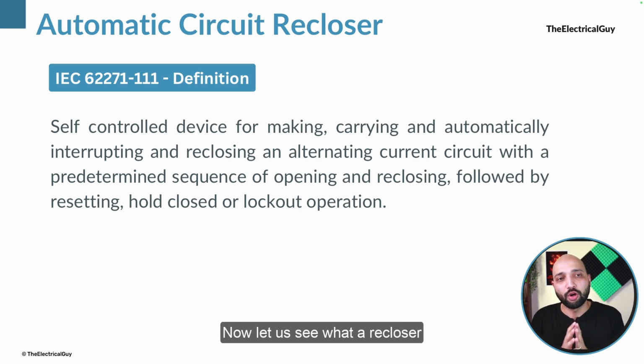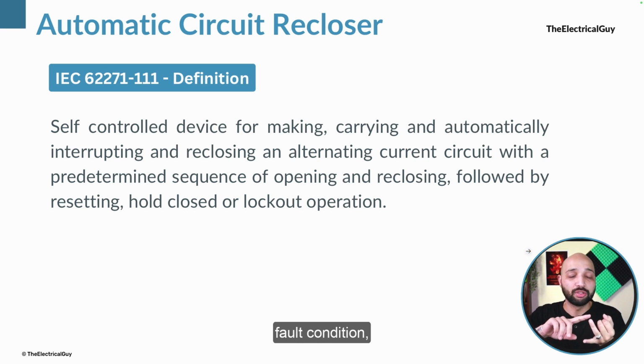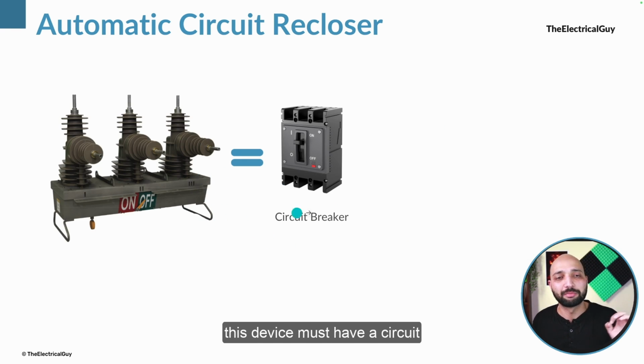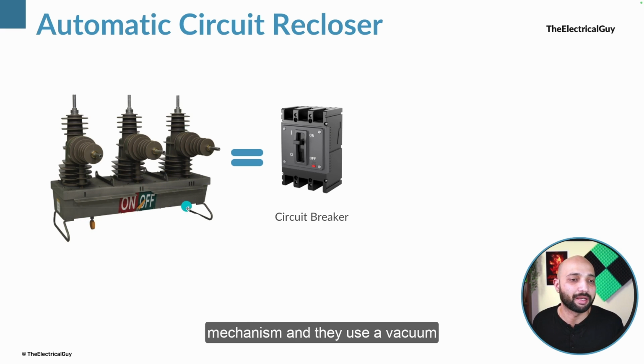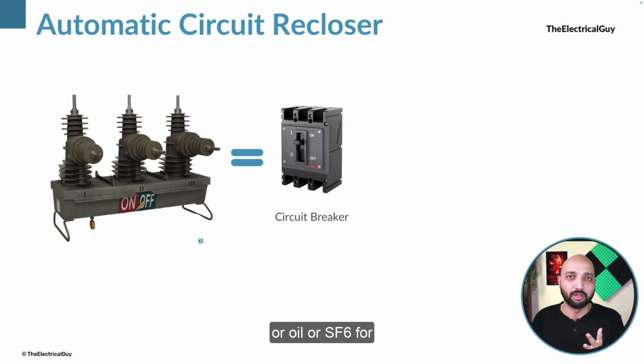Now let us see what a recloser consists of. Now we have seen by the definition it performs the functions like opening during the fault condition, sensing the fault condition, and also reclosing, right? So first of all, this device must have a circuit breaker, right? That is the basic need to open and close the circuit. So here you can see this is the insulator in which there will be an interrupter which interrupts the fault current and also the normal system current. So this is for R phase, Y phase and B phase. And of course, to operate this interrupter, there will be a mechanism, and they use a vacuum or oil or SF6 for interruption purpose.